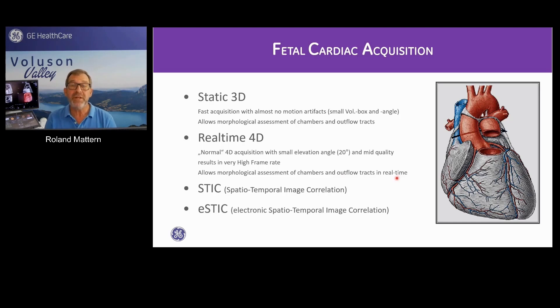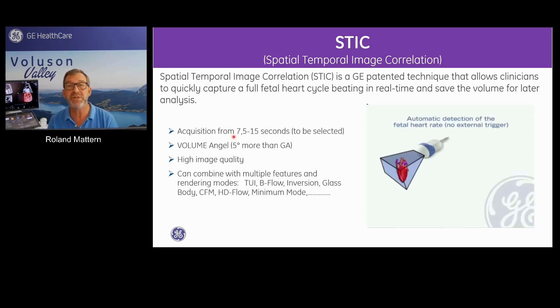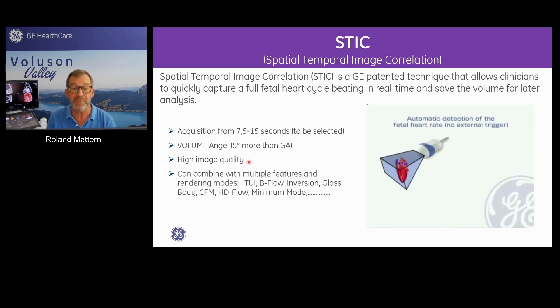The next step is STIC and E-STIC. On STIC, you set up the system with the acquisition time, which can be selected between 7.5 and 15 seconds. You should choose the correct volume angle - 5 degrees more than the gestational age - at high quality. This can be combined with multiple features and rendering modes like TUI, B-Flow, Inversion, Glass Body, and so on.